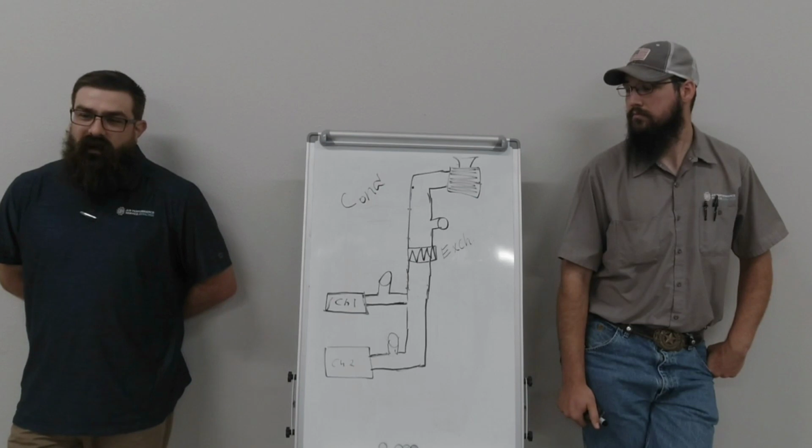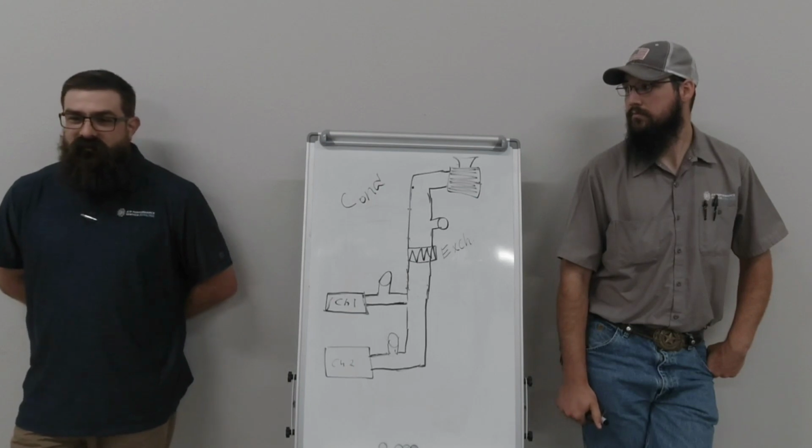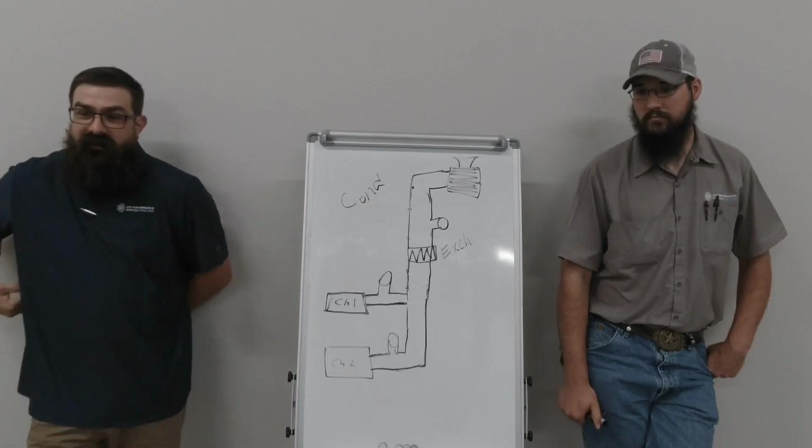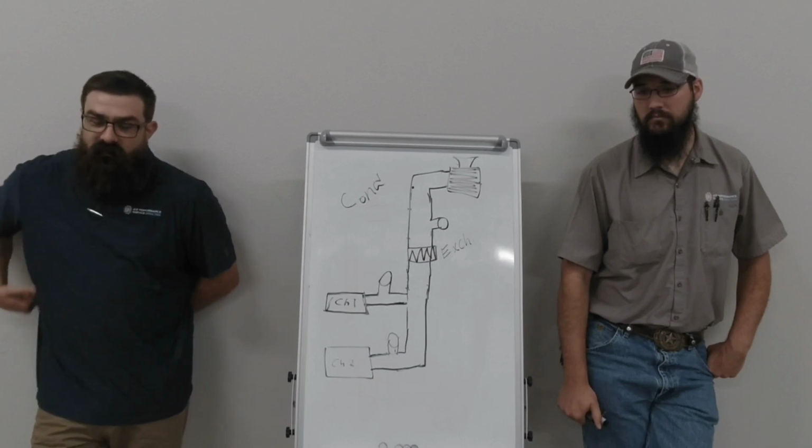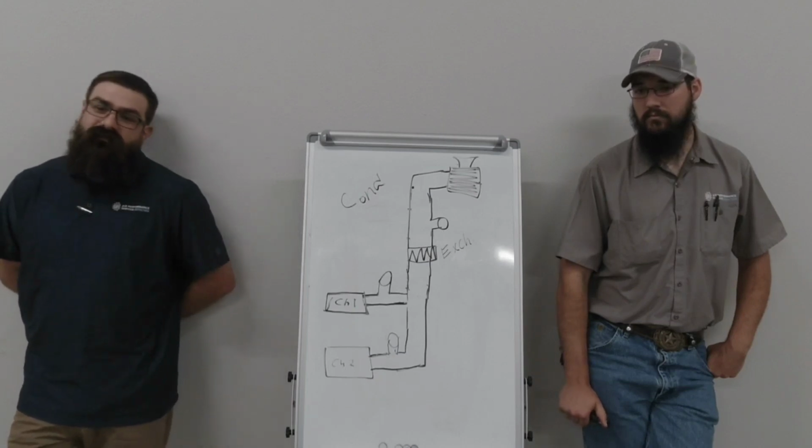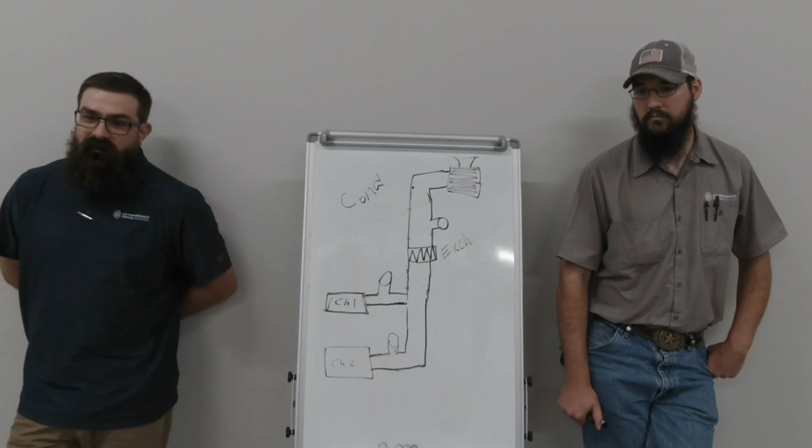So it's real popular in high energy consumption places where they get dinged for energy during the day. They'll run everything at night, super cool it all, and then during the day they can use the stored energy, so they're not getting charged high kilowatt hours.